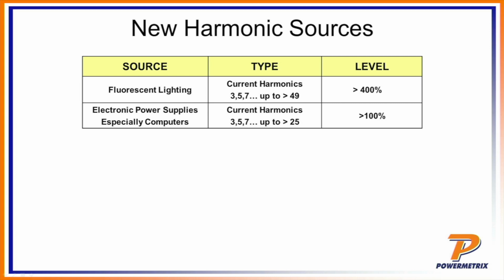One thing I didn't mention was how do we measure that? The normal units of harmonic energy are THD, total harmonic distortion. And really, that number is a ratio of harmonic energy to fundamental energy. In other words, fundamental would be 60 hertz energy, which is doing most of the useful work, and the harmonic energy, once again, is not doing useful work. It's typically being burned up as heat. And so, as such, I can have a THD level of greater than 100%, meaning that more harmonic energy is being put into my load than fundamental energy. And a lot of times, as I said before, that's being given up as heat, causing your equipment to overheat and cause all sorts of failures.